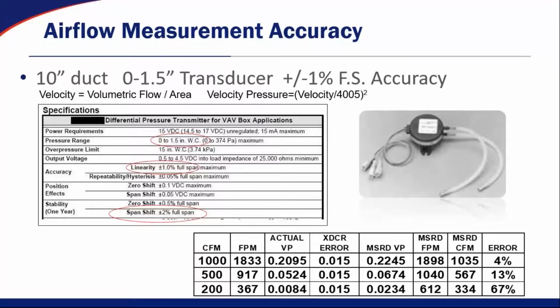Now, if you look at the velocity pressure versus the error, those two numbers are getting very close to each other. So when you add the error onto the velocity pressure, my measured velocity pressure is now 0.0234. My measured velocity is 612. Measured CFM is 334. And now I have a 67% error on my airflow control. So in this particular device, if you wanted to maintain about a 10% accuracy, you can only get about a 2-to-1 turndown ratio. Once you go to a 3-to-1, 4-to-1, 5-to-1 turndown, and you get below that 400 to 500 CFM range, your accuracy is going to drop off to an unacceptable range.